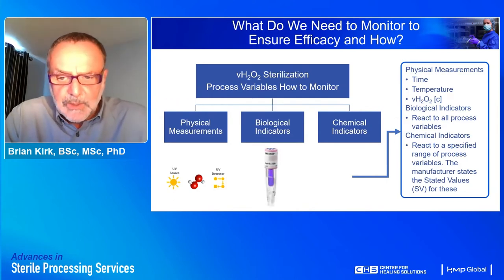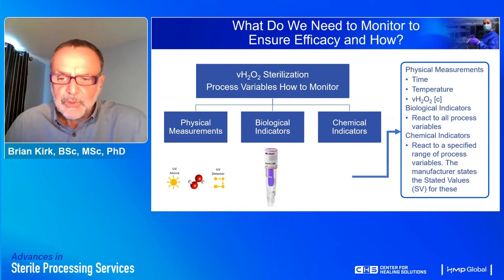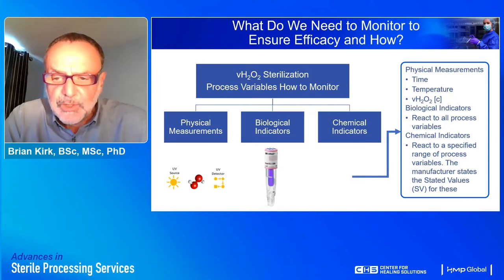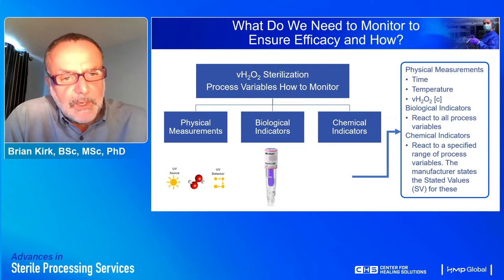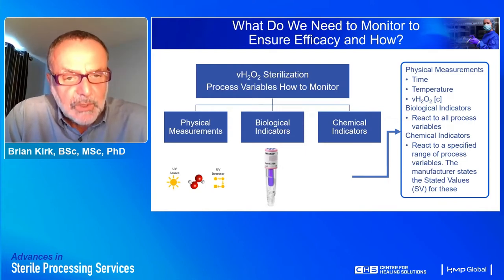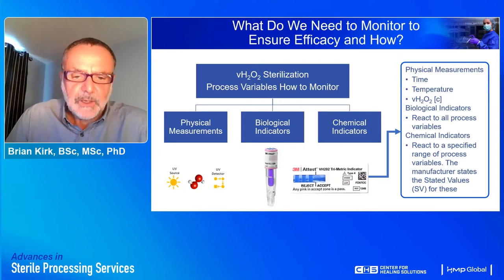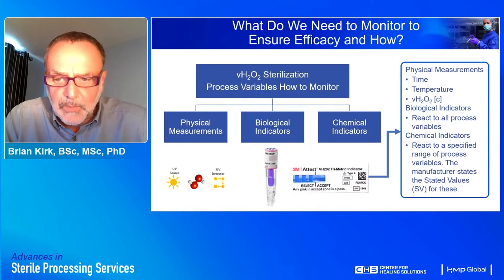Biological indicators are preparations of living microorganisms — usually a bacterial spore with a defined, calibrated resistance to the process — that are ultimately inactivated by the process. Biological indicators will react to all of the critical process variables. We also have chemical indicators, which usually give some kind of color change and respond in a defined way to the process they are monitoring.